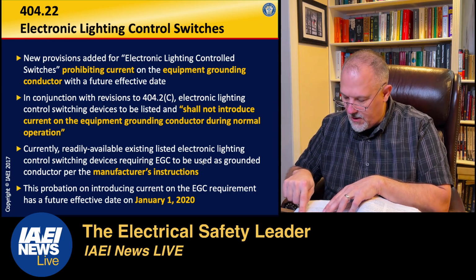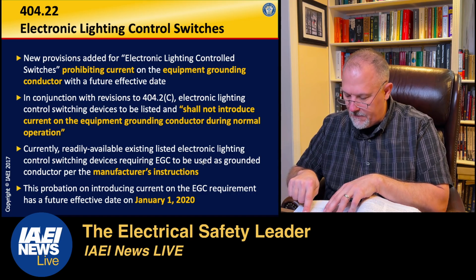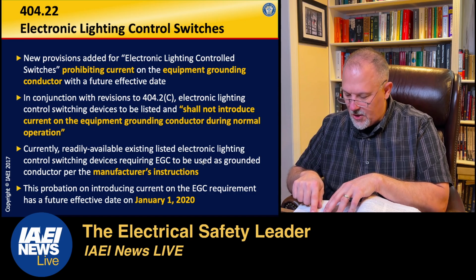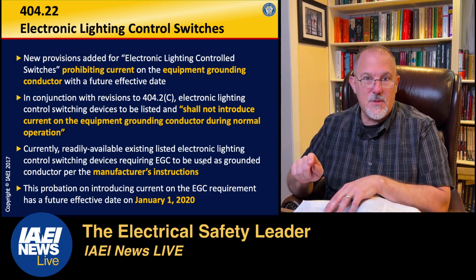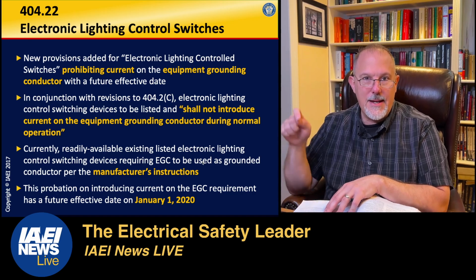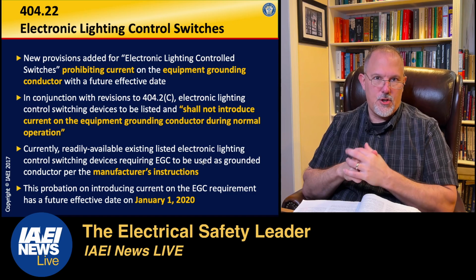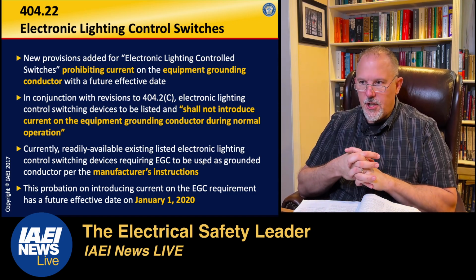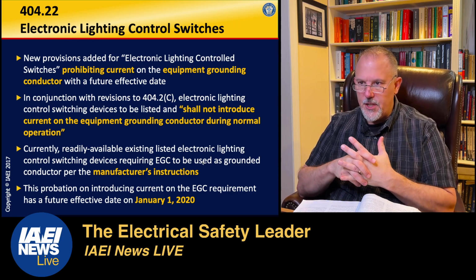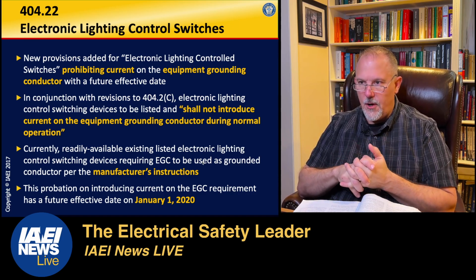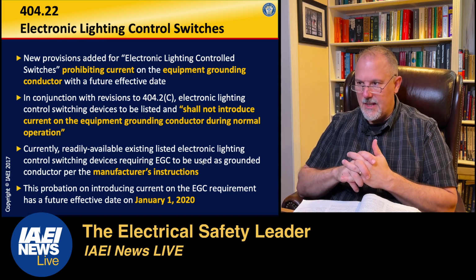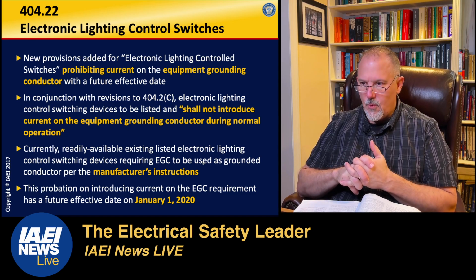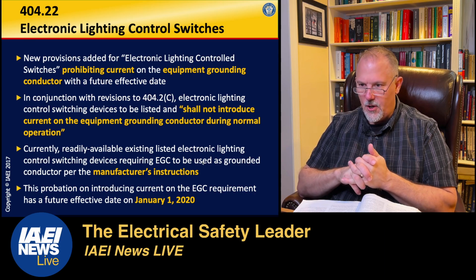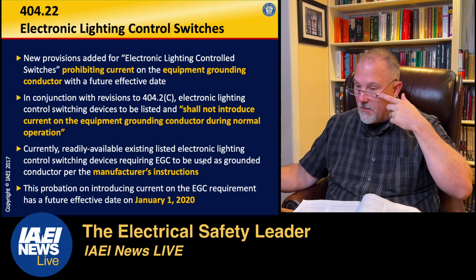And shall not introduce current on the equipment grounding conductor during normal operation. The requirement to not introduce current on the equipment grounding conductor shall take effect... What does that tell you? That means people had product that used the equipment grounding conductor. And they gave you a stay of execution, 3 years. In conjunction with the revisions of 404.2c, electronic lighting control switching devices to be listed and shall not introduce current on the equipment grounding conductor during normal operation. Currently, readily available existing listed electronic lighting control switch devices require the EGC to be used as grounded conductor per the manufacturer's instructions. This prohibition on introducing current on the EGC requirement has a future effect.